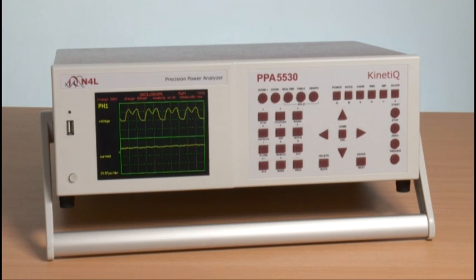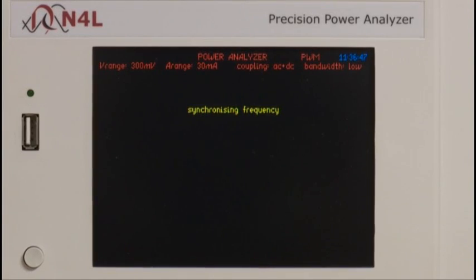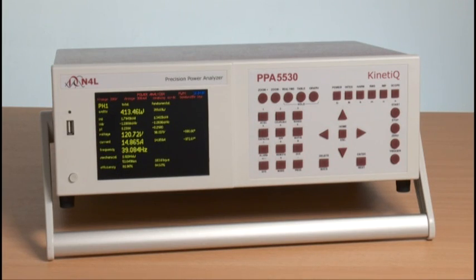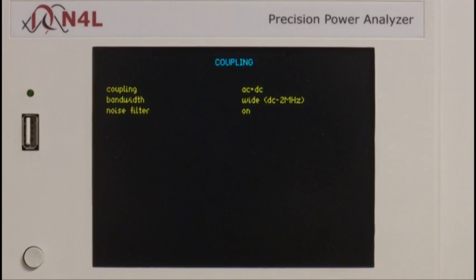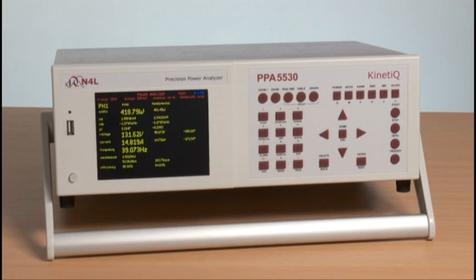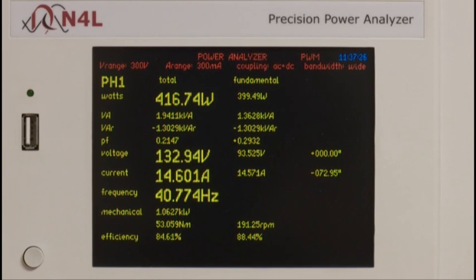It can easily be seen that the waveform rise time has been significantly reduced by filtering. This will inevitably influence the accuracy of total power measurement. We can illustrate this by looking at the voltage in the power screen while still in low bandwidth — we have a nominal 120 volts phase to neutral. If we reselect wide bandwidth giving DC to 2 MHz, the voltage increases to 131 volts. So we have approximately 10 volts difference due only to frequency components above 30 kHz. Since switching frequency components are present in both the voltage and current signals, it is clear that filtering will reduce the accuracy of wideband measurements.